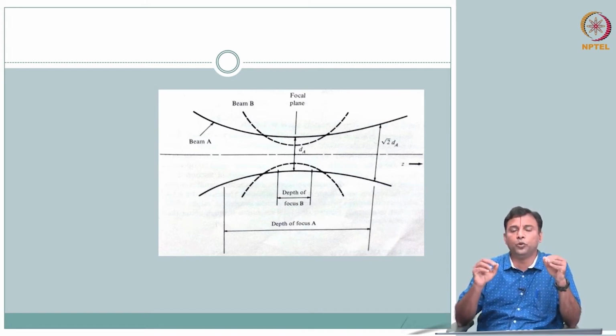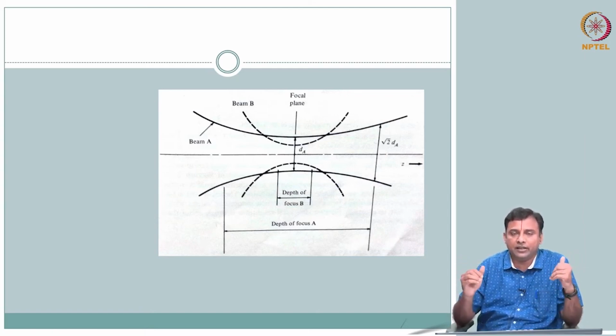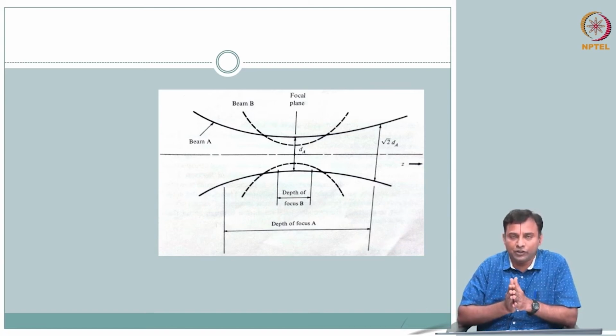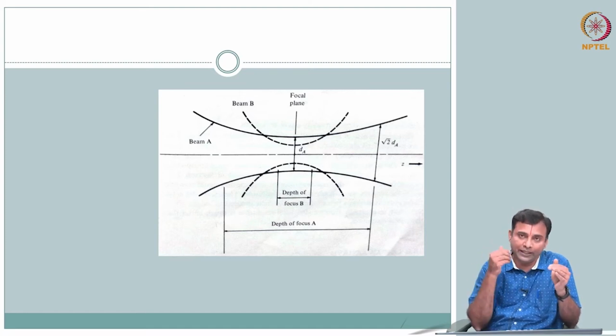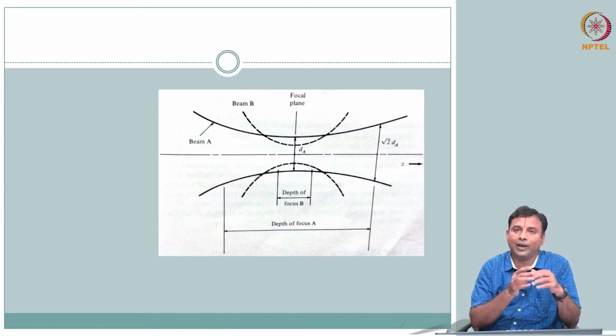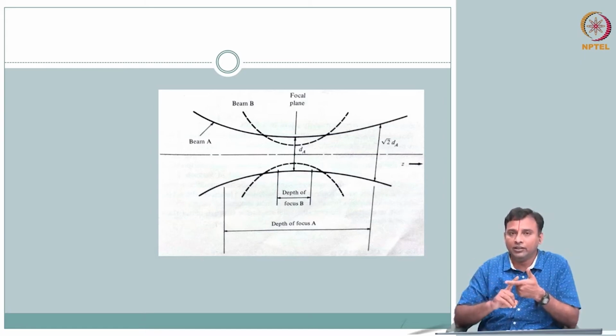There is a lot more to do with engineering a transducer depending on the application. Okay, but for now what we will do is we will convince ourselves that at an introductory level we know what an ultrasound transducer is, and it allows us to both generate an ultrasound wave and send it into the body, right, because you have the matching layer, remember. So you send it into the body and whatever comes back it is able to receive, convert it into electrical quantity.